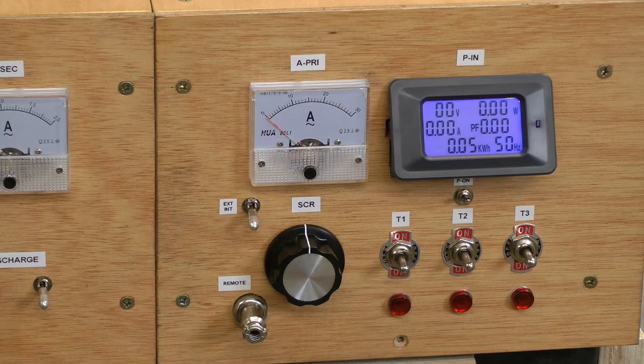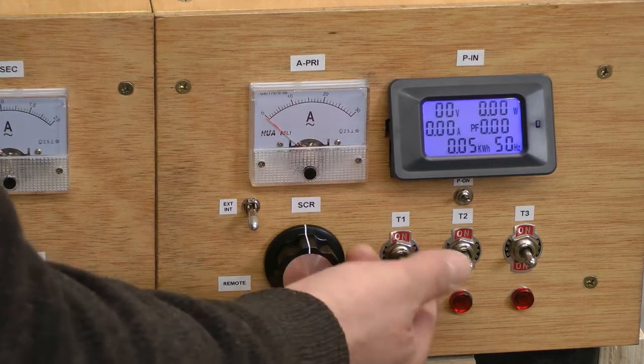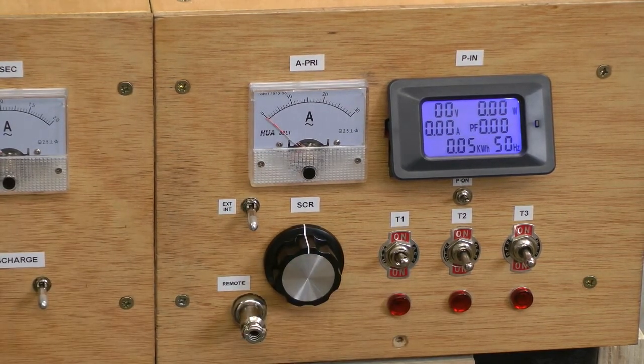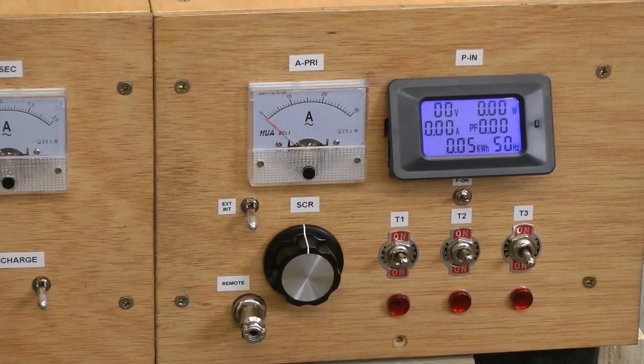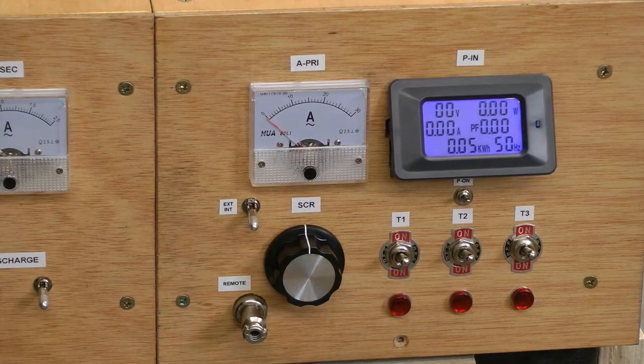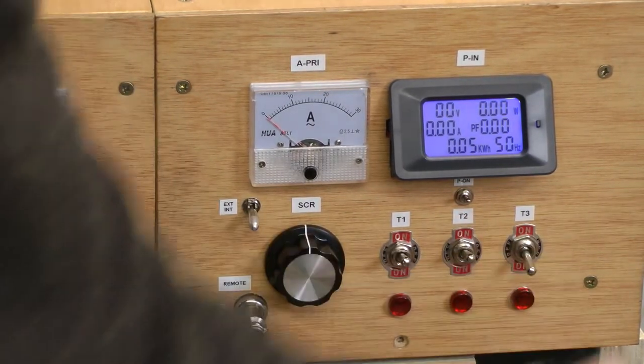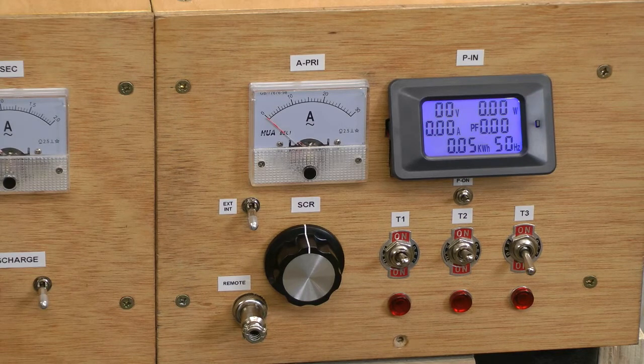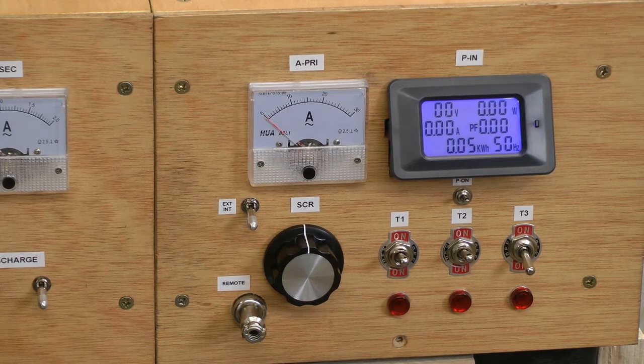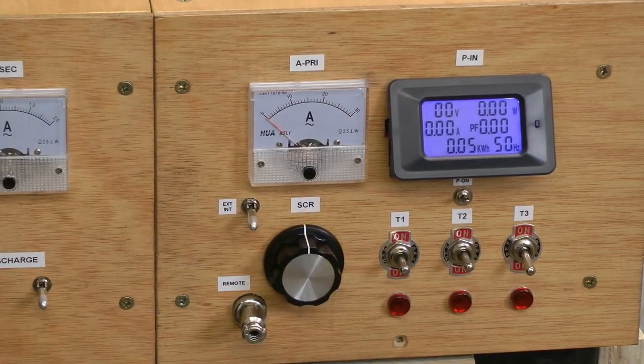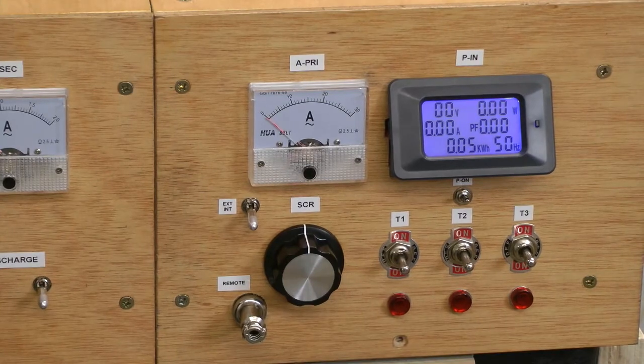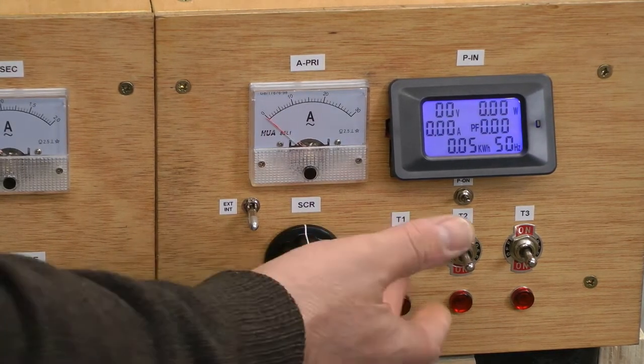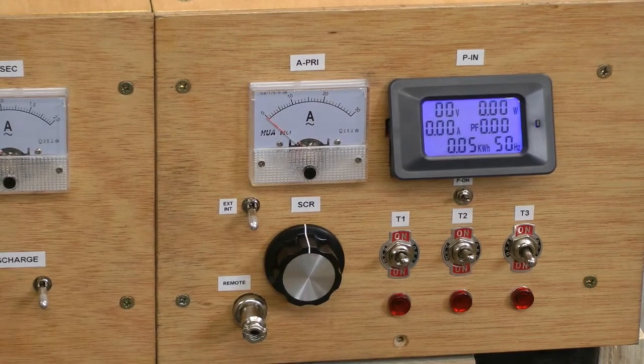we combine transformers. So in other words, if we were to put one transformer on, we could push it upwards. If we wanted to bring another transformer in parallel on, we push another one in the same phase and a third transformer in parallel, all in the same phase. What we wouldn't do is put 3 transformers in parallel and put one of them anti-phase, because then they will basically be pushing against each other. One is in phase, one is out of phase. On the other hand, if we want to run 3 transformers in series, or 2 transformers in series rather, we might put 2 transformers in series like that.